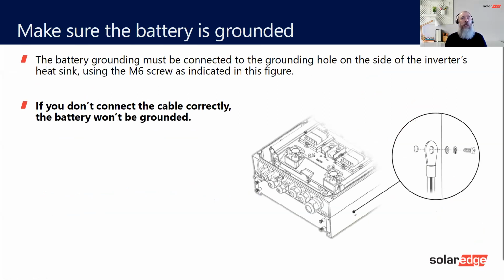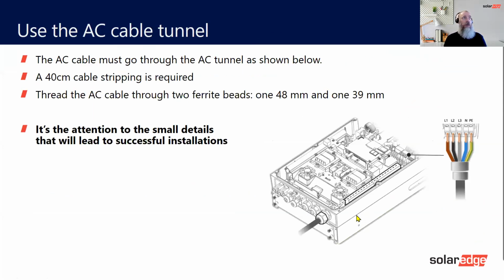We also have a battery grounding screw, and you can locate that on here, just on the casing of the inverter. And obviously, if you don't connect the cable correctly, the battery won't be grounded. Use the AC tunnel. I've already showed you where this was. This is the part that lifts out. The cable is then routed through, and you terminate it here and put the cable back. So put the AC tunnel back.